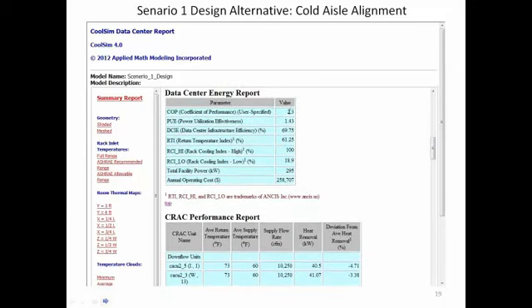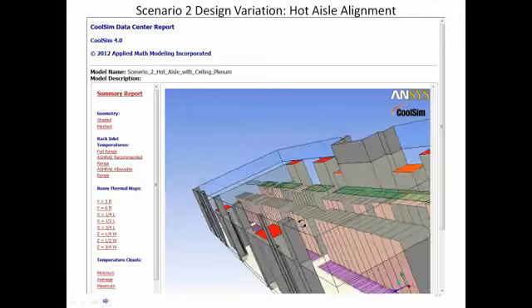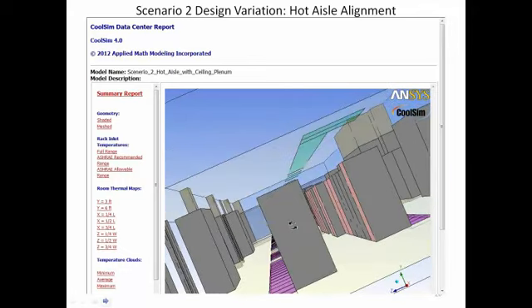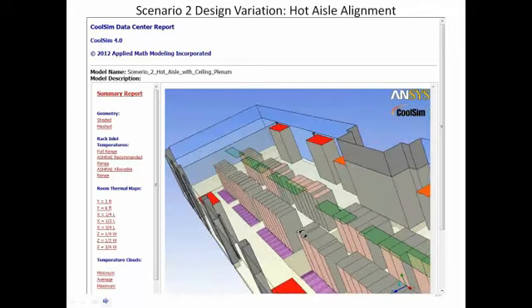This one's a hot aisle. Yes. This one here, we wanted to give them the option of a return plenum, which would allow better distribution of the hot air to the CRACs, and also from no short cycling. So what you've done here is right down the center, you've basically changed the racks into the other direction. They're all now cold on the front side, blowing hot to the center. So instead of the center being a cold aisle, the center is a hot aisle here. And you're using a return ceiling plenum. It's probably a drop ceiling in place right there, right? Correct. So in terms of expense, this isn't too bad.